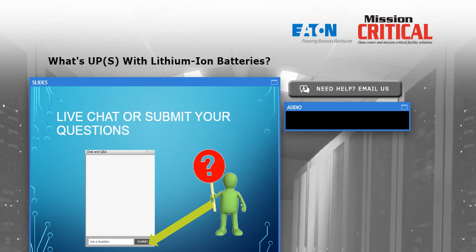Is the lithium battery fail gradual over time where you can predict a failure? In our experience, yes. Just like valve-regulated lead-acid batteries, we're looking generally for that 80% capacity point, and it does gradually roll off over time. So it's not the kind of thing where I'll be at 85% capacity for 9 years, and I'll lose that last 5% in the 10th year. It is a gradual roll-off. However, the preliminary data that I've seen does not show much, if any, degradation, for example, in the first 5 or 6 years.